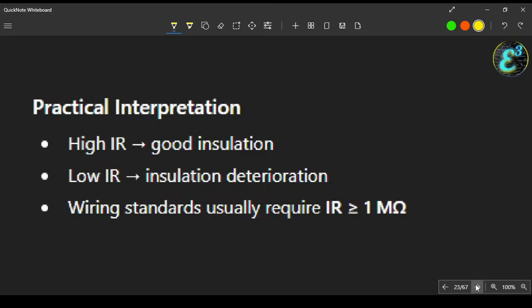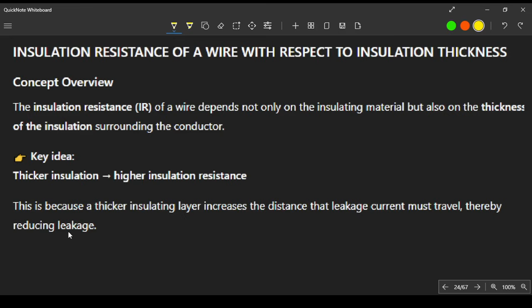Insulation resistance of a wire with respect to insulation thickness: the insulation resistance of a wire depends not only on the insulating material but also on its thickness. Key idea: thicker insulation means higher IR or higher insulation resistance. This is because a thicker insulation layer increases the distance that leakage current must travel, thereby reducing leakage. So if the insulation is thicker, the leakage current, in case of a short circuit or other fault, will have a greater distance to travel, thereby reducing the leakage current.